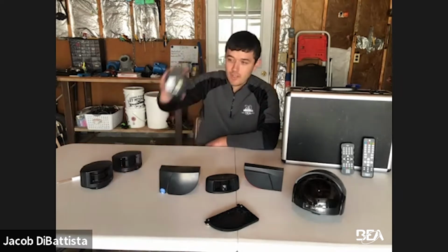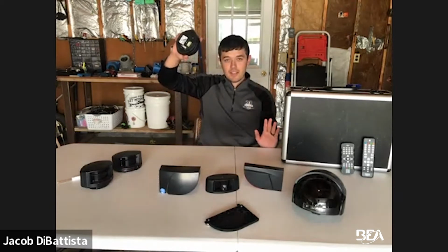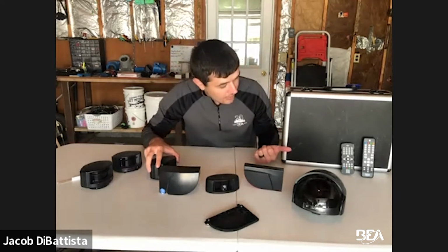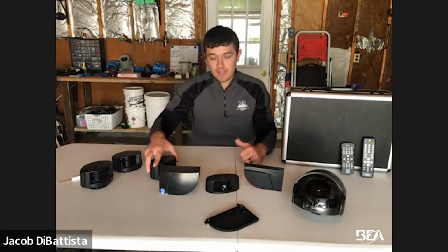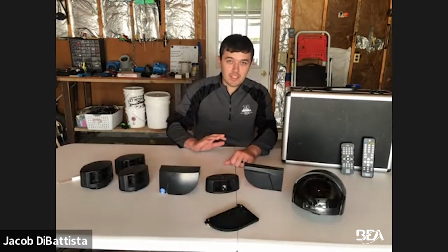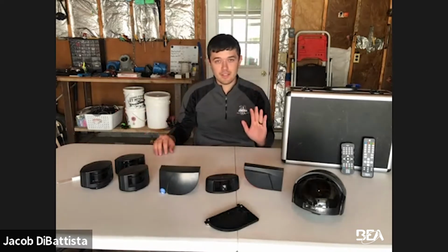So let's say you have this up on the corner, and I want to choose right here that if I put my hand, it's going to send a signal to open that door, just like a regular push button. You can program that with one of these remotes that have the colors on the bottom or on the top. And then that's going to tell the LZR, ignore detection all around this field to open the door, except for where I put my hand.